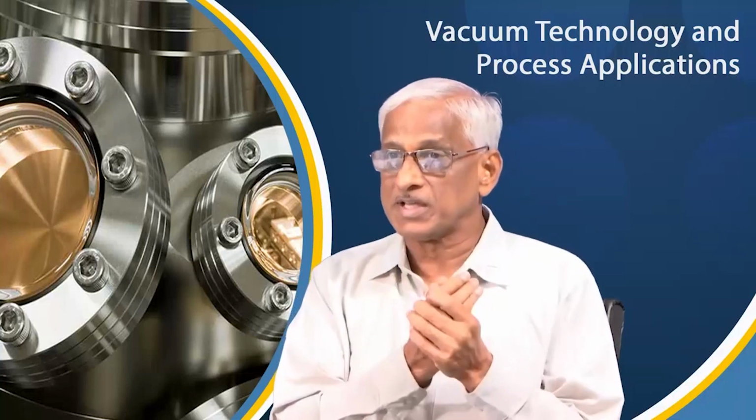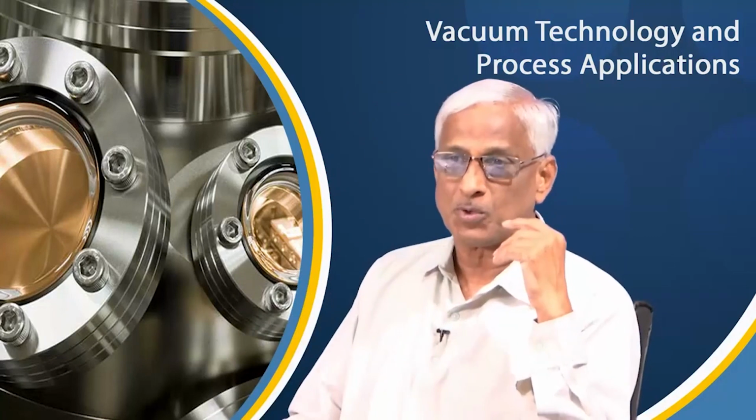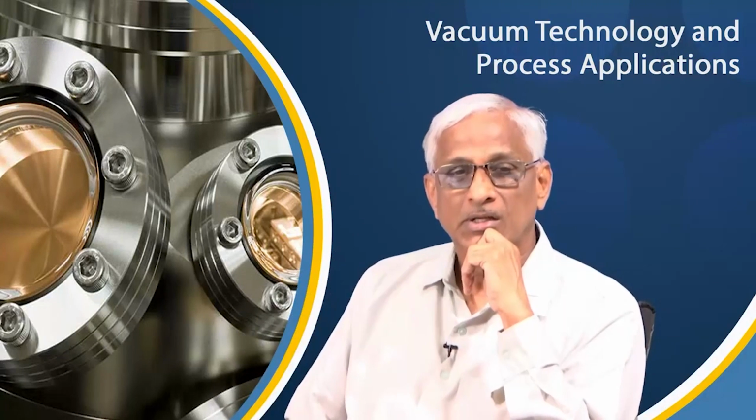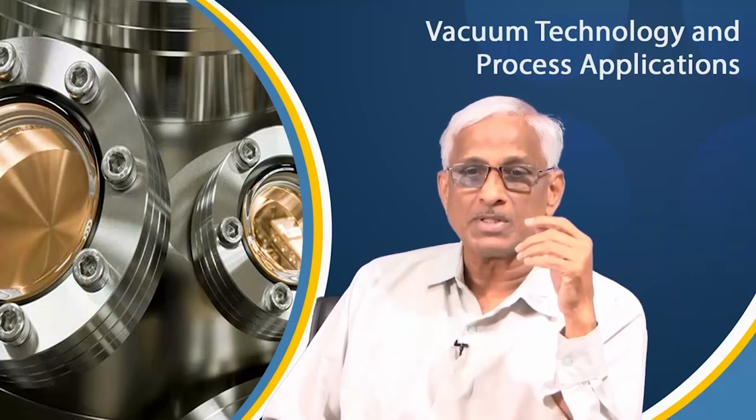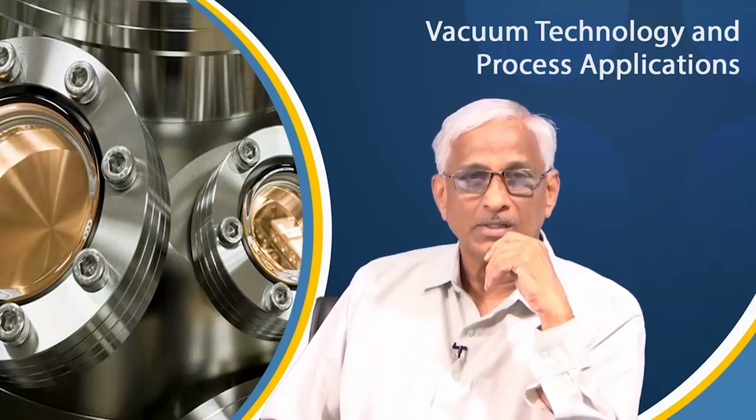For example, even in low and medium, it is not just only the value of vacuum, it is dryness. For example, of late last 15-20 years, the dry pumps like screw pump, roots blower of course is there earlier also, now also it is getting more and more popular as a booster, and claw pumps and scroll pumps, they are becoming very popular.